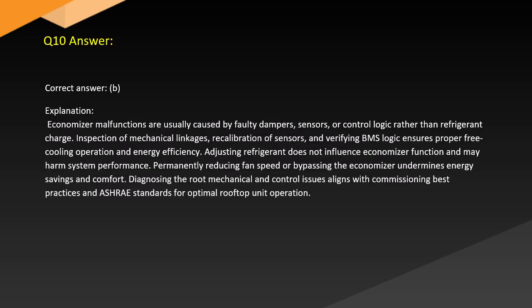Answer. Correct answer: B. Explanation. Economizer malfunctions are usually caused by faulty dampers, sensors, or control logic rather than refrigerant charge. Inspection of mechanical linkages, recalibration of sensors, and verifying BMS logic ensures proper free cooling operation and energy efficiency. Adjusting refrigerant does not influence economizer function and may harm system performance.